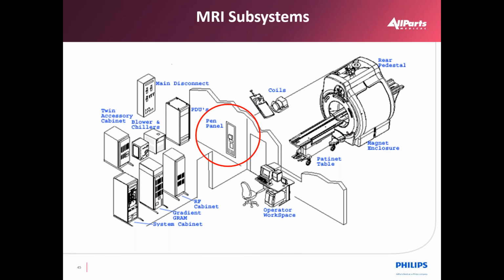The penetration panel, or pen panel, is a connection panel that provides a point of entry for the cables coming from the equipment room into the scan room. This is used to allow a pass-through point for these cables, preventing stray RF from entering the room.